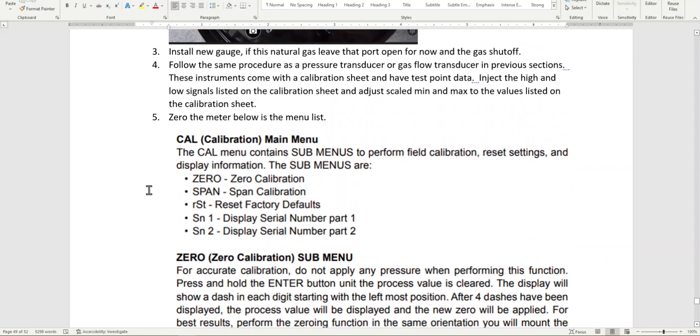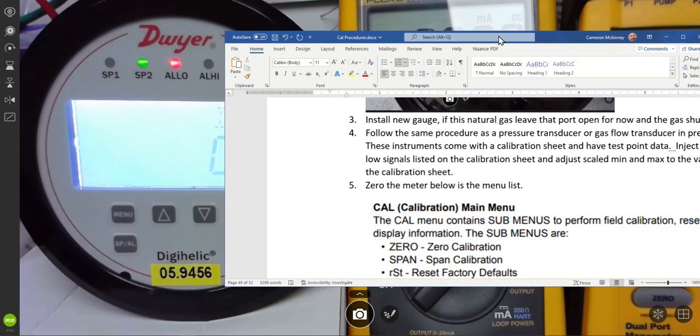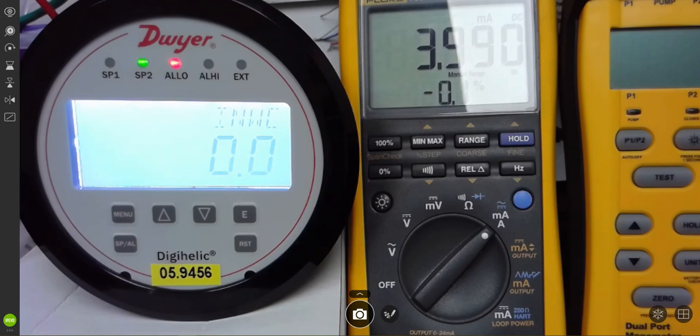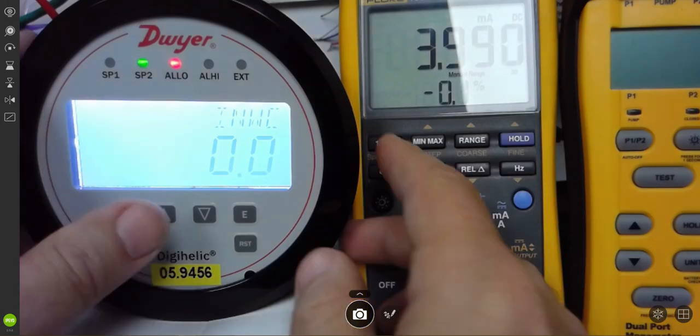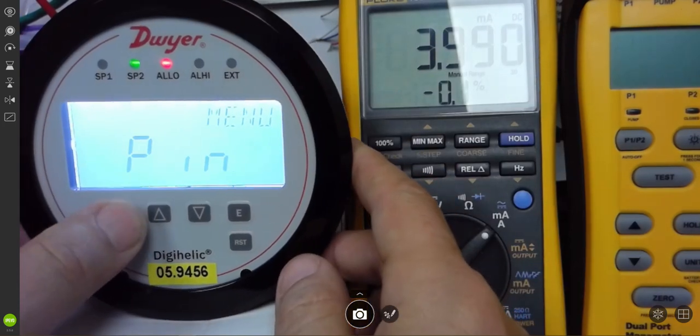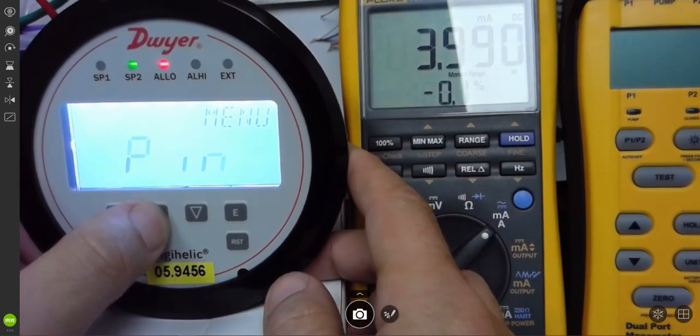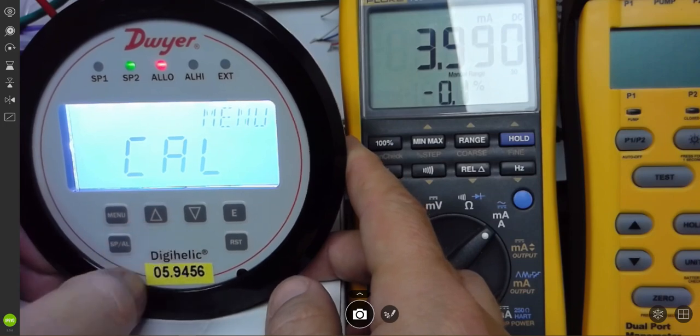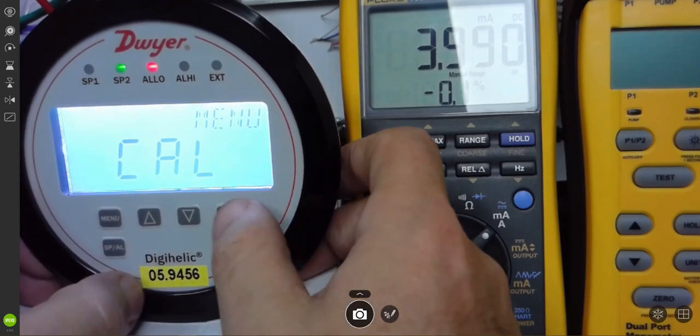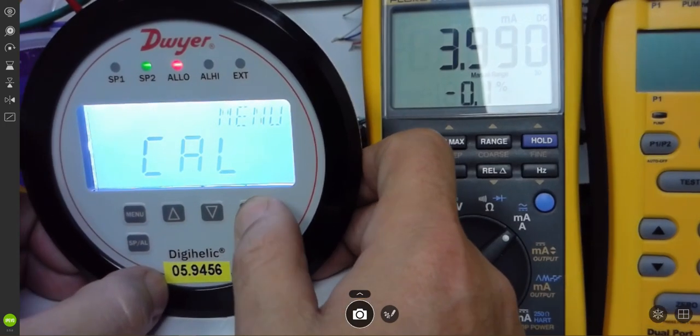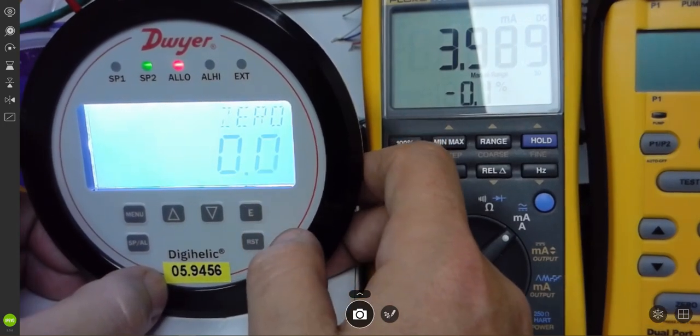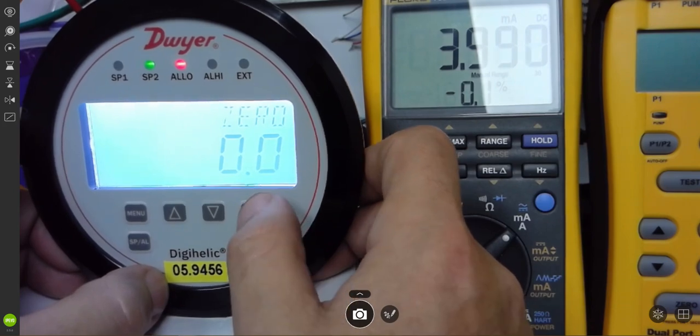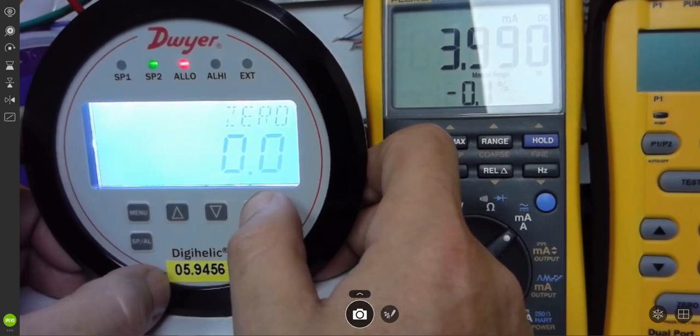First thing we're going to do, we're going to start this video at zero. We're going to calibrate the meter. You should have hooked this up and played with it before you go out there and try to do this on the line. So we have these available and you have your test bench. We're going to hit the menu button. Hit the up arrow. Now we're in the cal menu. We're going to hit the E for enter. I'm going to hit enter to zero this meter out.